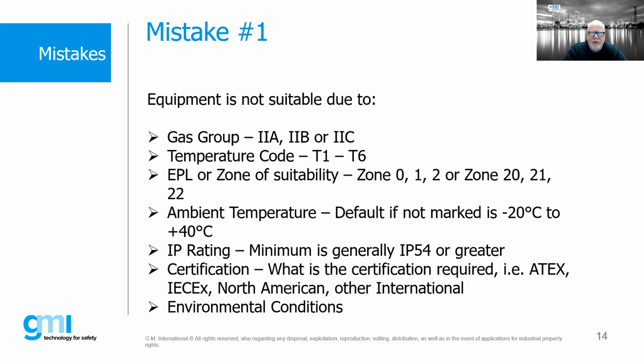And we understand this. One thing that comes up is ambient temperature. The default for all EX equipment is -20 to +40. But I know in many parts of the world, +40 is not that terribly hot. We get above +40 in the Gulf of Mexico, offshore markets quite a bit during the summertime. And certainly in the Middle East, it's not unusual to see +50 or +60. So we have to be aware of that. Remember, EX equipment, unless it's marked, will always be for -20 to +40.